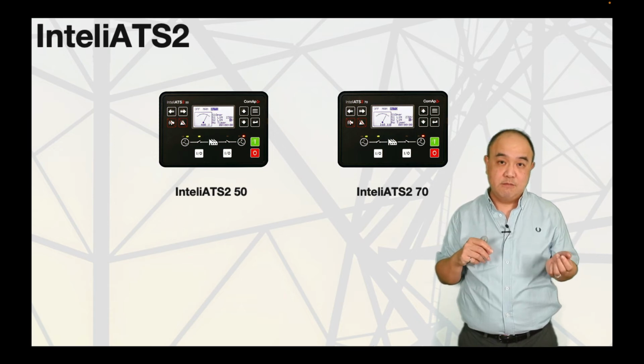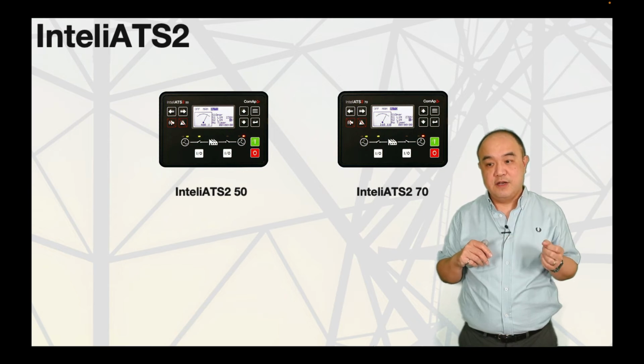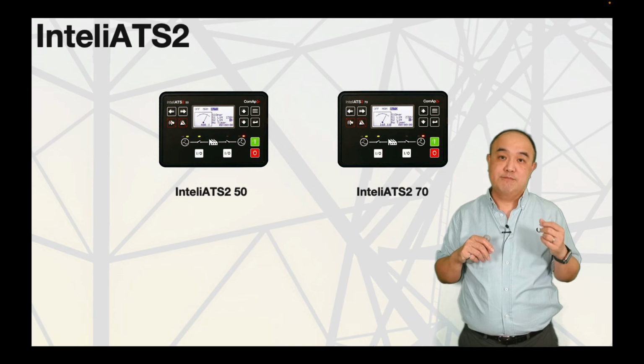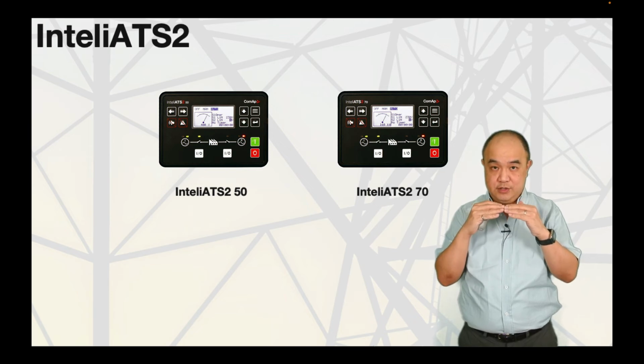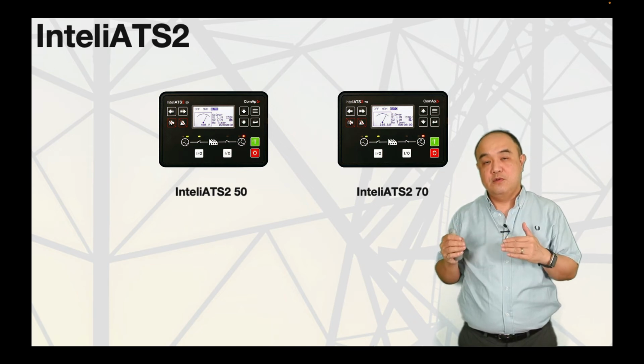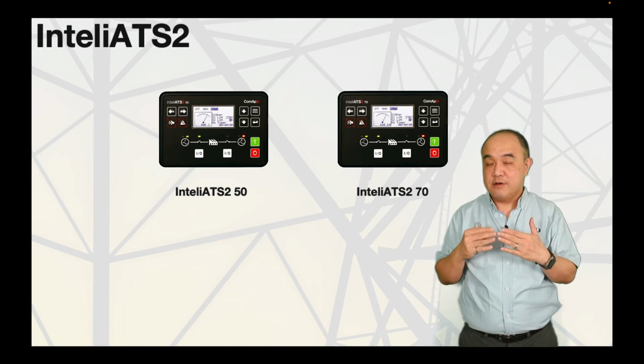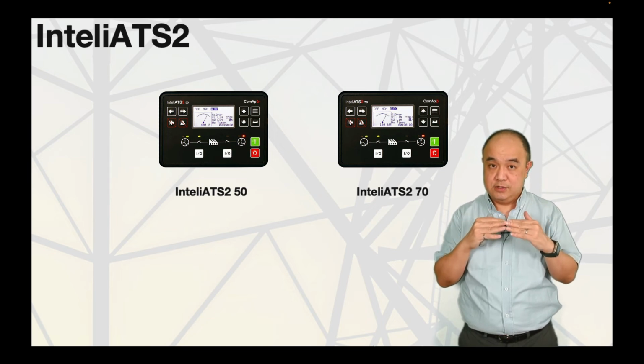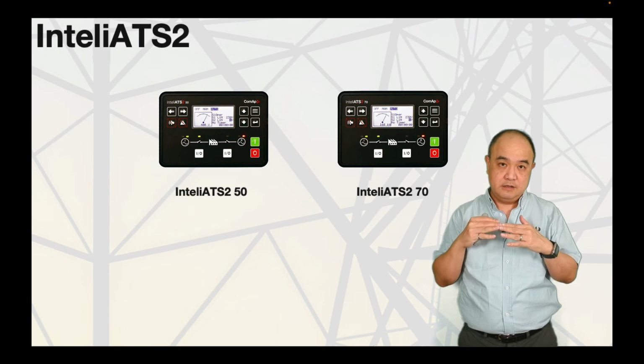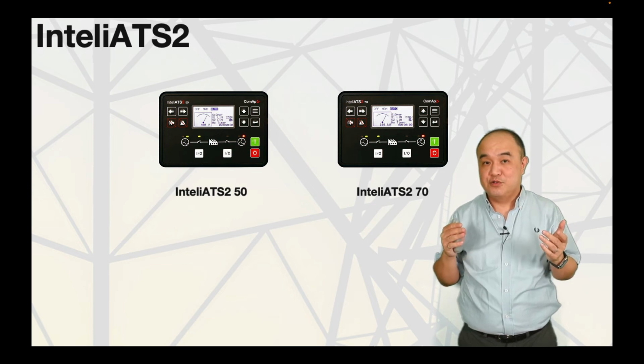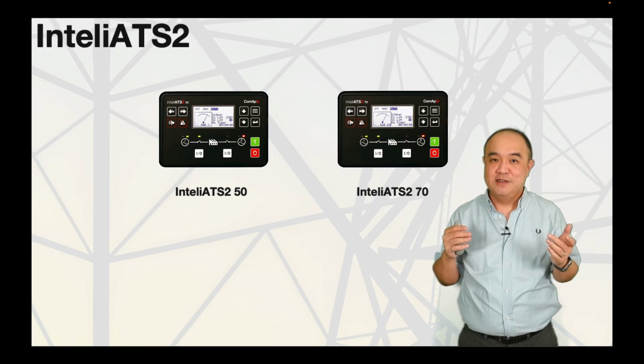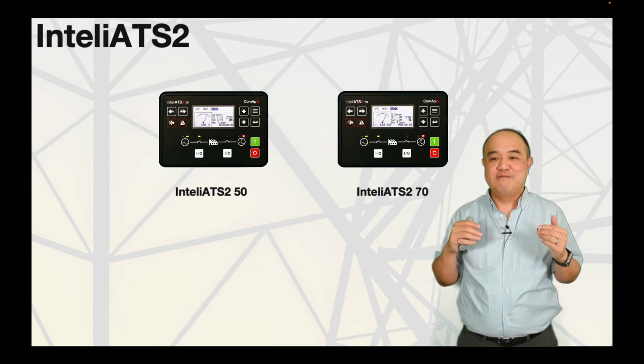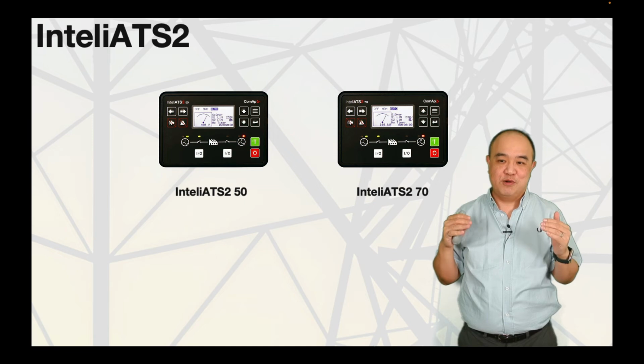We call it an elevator switch. This is available for the 50 and 70 models. One thing to watch out for: in the old InteliATS Power, there was a close transition function. In the new 70 model, this function is not there. So if you still need close transition, you'll have to use the old InteliATS Power. If you don't know what close transition is, you're probably not using it, so don't worry too much. Everything else is supported in the new one.